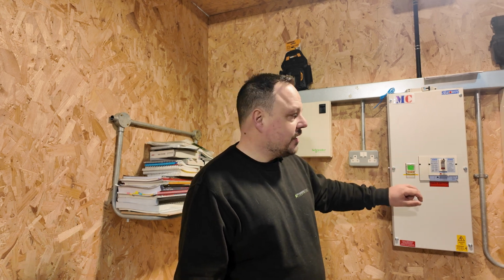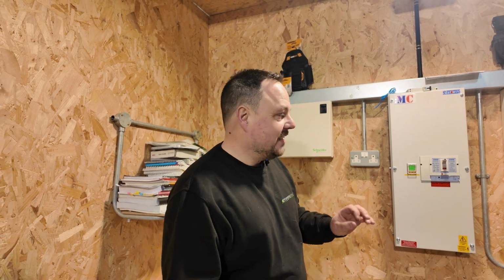So it is two different component parts within this enclosure. You've got your MCCB here, which is the 160 amp variant with massively undersized cables, it has to be said. And that is looking for your overload and short circuit faults. So if you get line and neutral touched together, it's going to be this that sees that and operates. Same if you have a consistent overload, something's going on in the circuit. We could end up putting loads of different final circuits out of this distribution board, and the final sum total of all of that draw operates this.